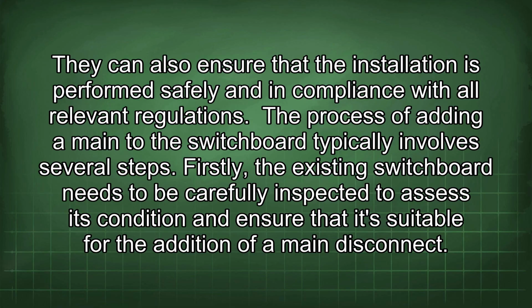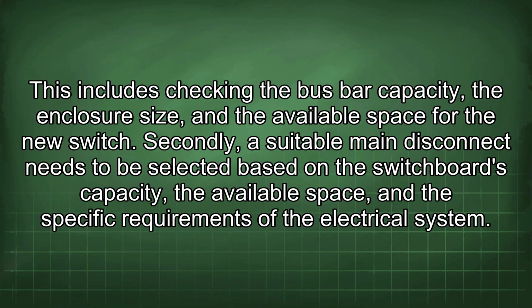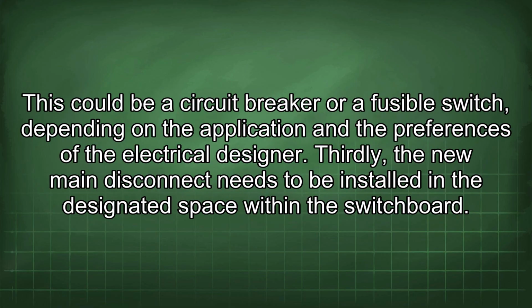The process of adding a main to the switchboard typically involves several steps. Firstly, the existing switchboard needs to be carefully inspected to assess its condition and ensure that it's suitable for the addition of a main disconnect. This includes checking the bus bar capacity, the enclosure size, and the available space for the new switch. Secondly, a suitable main disconnect needs to be selected based on the switchboard's capacity, the available space, and the specific requirements of the electrical system. This could be a circuit breaker or a fusible switch, depending on the application and the preferences of the electrical designer.